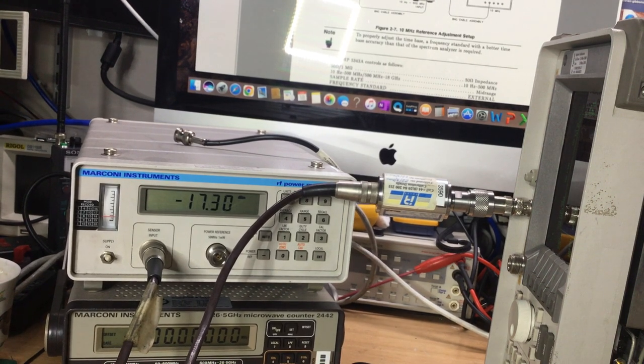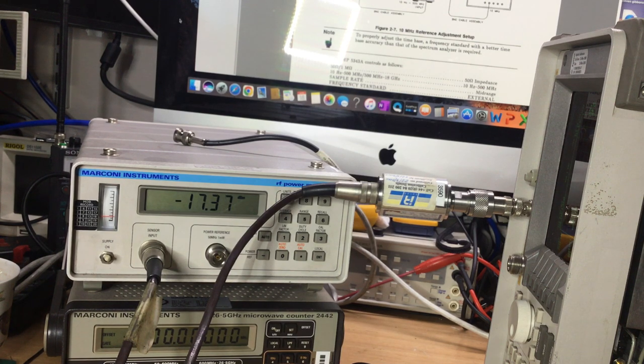So there's something majorly wrong with both the level and also the data. Now, if I turn it counterclockwise, obviously we're getting to minus 20 dBm and beyond. It's a slow adjustment, but fully clockwise now, we can't get anywhere near minus 10 dBm. So obviously there's an amplitude issue as well as a frequency error issue. So with the DAC, could it be a supply issue potentially? That's when the supply voltages are low. I would have thought we'd get one, maybe not the other.